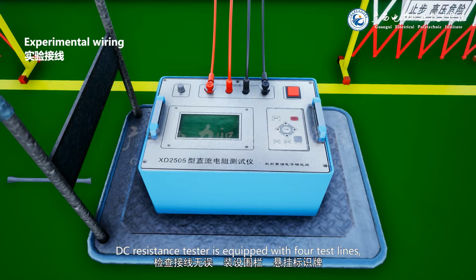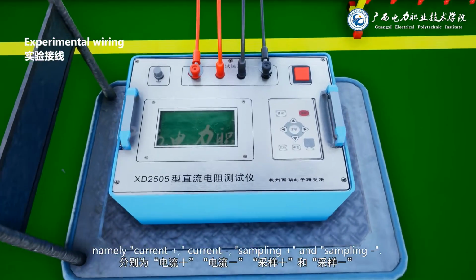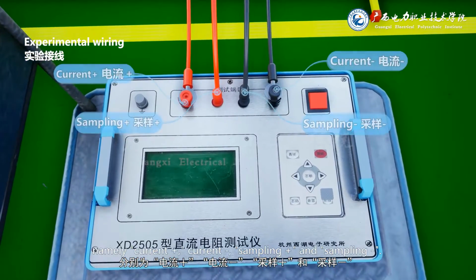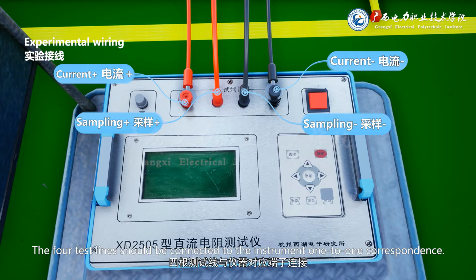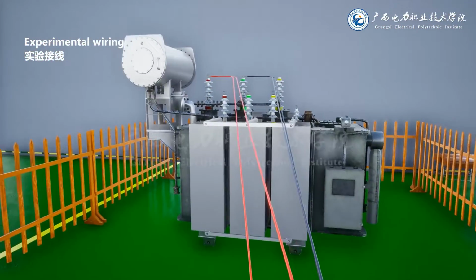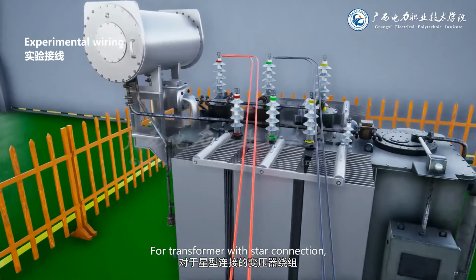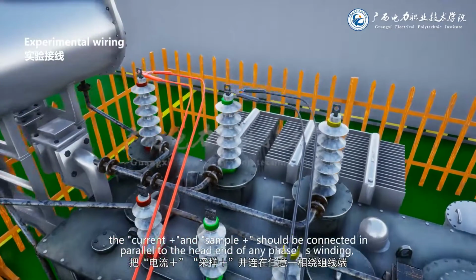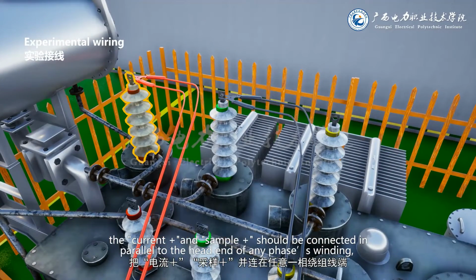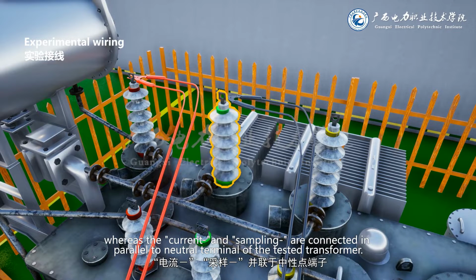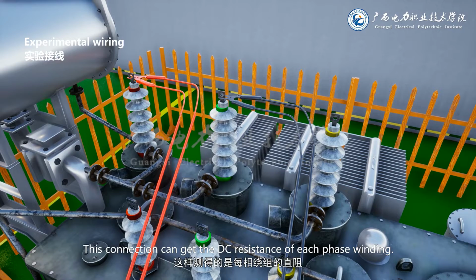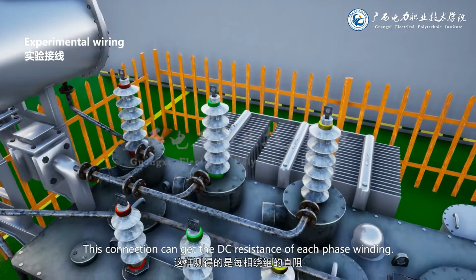DC resistance tester is equipped with 4 test lines, namely current plus, current minus, sampling plus, and sampling minus. The 4 test lines should be connected to the instrument one-to-one correspondence. For transformer with star connection, the current plus and sampling plus should be connected in parallel to the head end of any phase winding, whereas the current minus and sampling minus are connected in parallel to neutral terminal of the tested transformer. This connection can get the DC resistance of each phase winding.